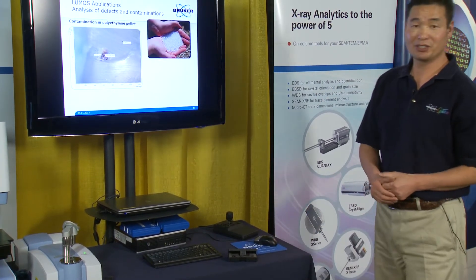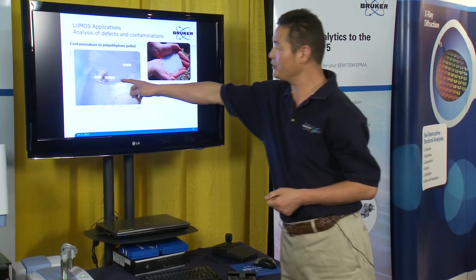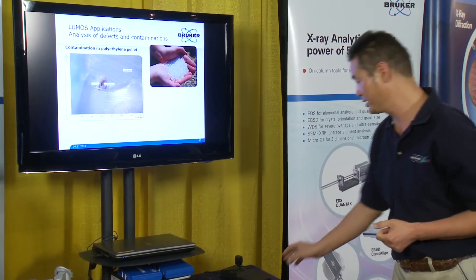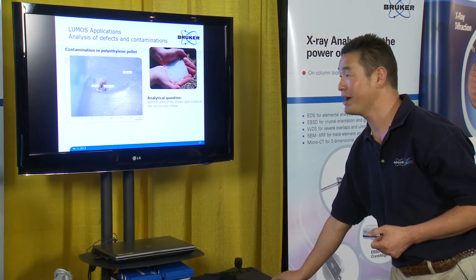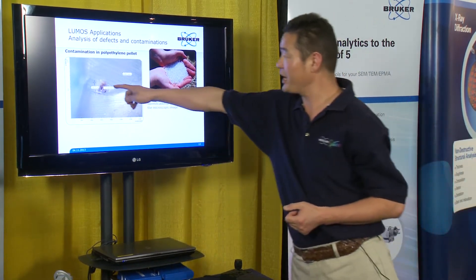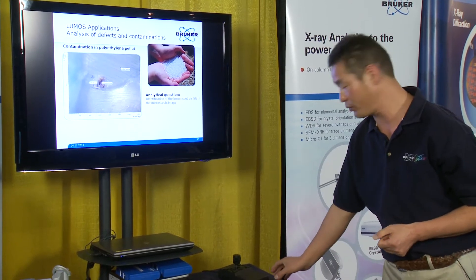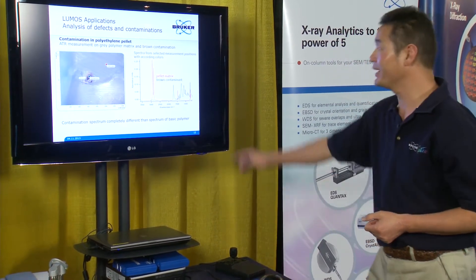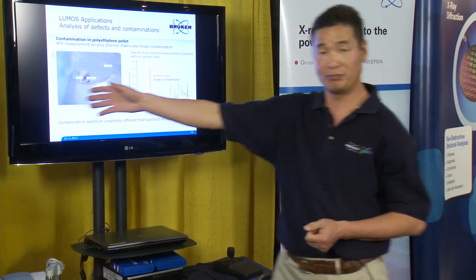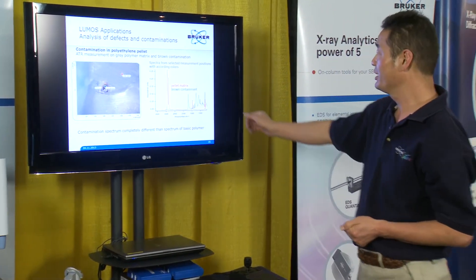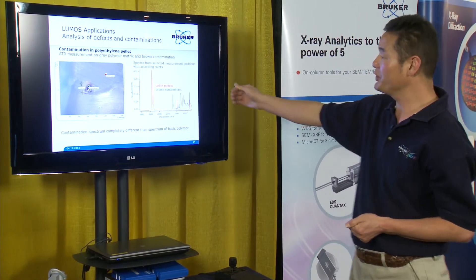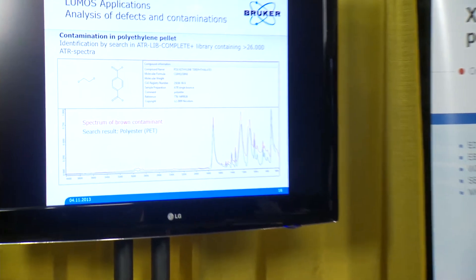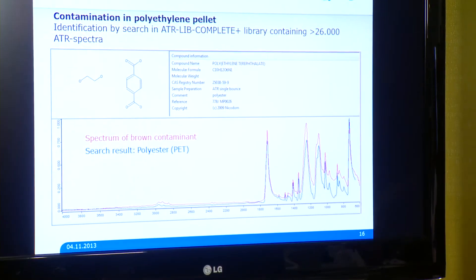Here's an example. If I have polymer beads and there's a little brown spot on one of them — what is that? It's a contamination. Using the microscope, notice the scale here is very small, only 180 microns. We can get the infrared spectrum from this in about 15 seconds. Library search gives you the correct ID of this sample as polyester, very quickly.